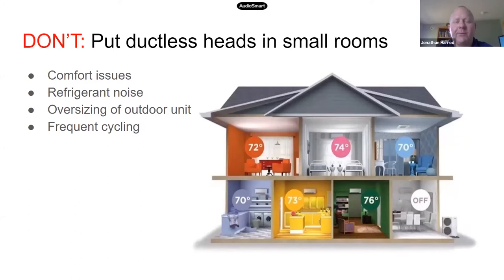Another big lesson that we've learned is don't put ductless heads in small rooms if you can avoid it. This picture comes from one of the manufacturer's websites, and you'll see it replicated all across the internet. And here they've got a ductless head in every single room. This is not best practice. Essentially, the smallest these heads are made is about 6,000 BTUs. But oftentimes, a small room like a laundry room or a home office might need a lot less than that. It might only need 2 or 3,000 BTUs.